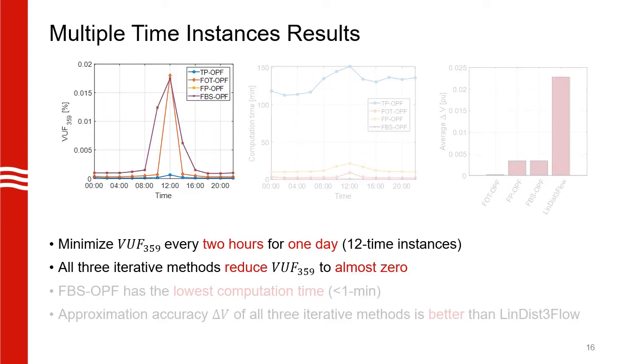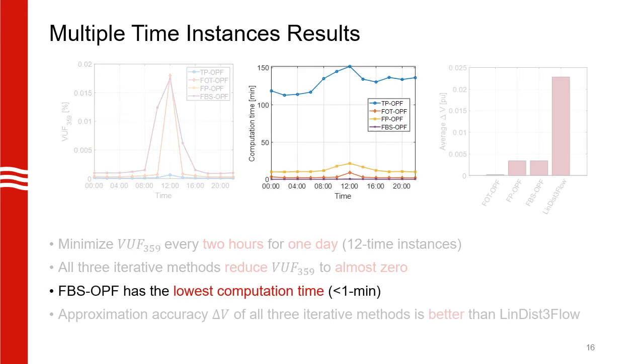Our next set of results are when we solve the OPF multiple times. In this case, we only minimize voltage unbalance at our critical node 359 and we do this every two hours throughout a single day. We can see from the objective values here that all three methods are able to reduce unbalance at our critical node to almost zero. If we look at the computation time, all three methods are significantly faster than TP-OPF with the forward-backward sweep converging to solutions in less than one minute. This is probably because it exploits the radial nature of the network, whereas the other two methods involve calculation of large matrices like the bus admittance matrix and the Jacobian.